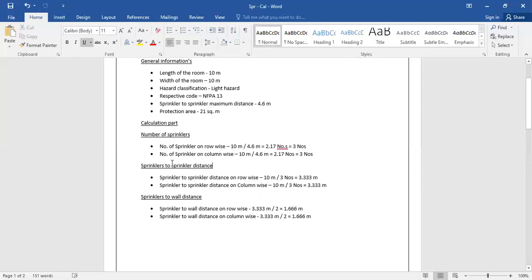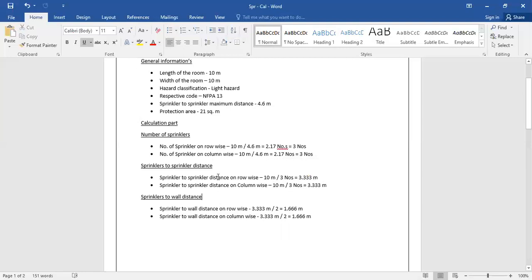Next, we find the sprinkler-to-sprinkler distance, which also contains two steps: row-wise and column-wise. For row-wise, we take the length of the room divided by 3 — the number of sprinklers we found — and we get 3.333 meters. For column-wise, dividing the width by 3 also gives 3.333 meters.